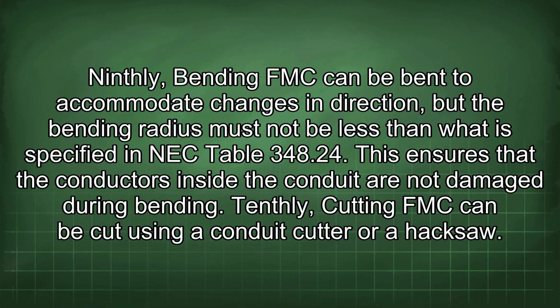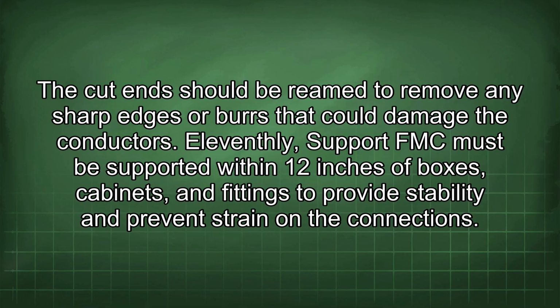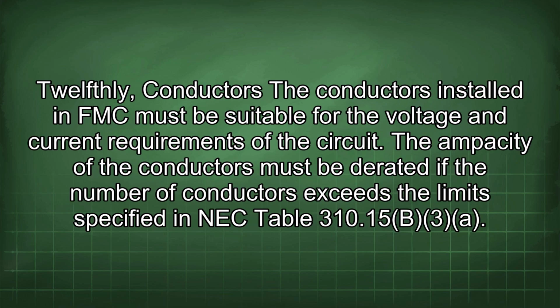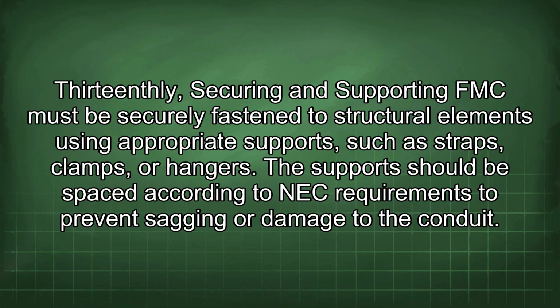Tenthly, cutting. FMC can be cut using a conduit cutter or a hacksaw. The cut end should be reamed to remove any sharp edges or burrs that could damage the conductors. 11thly, support. FMC must be supported within 12 inches of boxes, cabinets, and fittings to provide stability and prevent strain on the connections. 12thly, conductors. The conductors installed in FMC must be suitable for the voltage and current requirements of the circuit. The ampacity of the conductors must be derated if the number of conductors exceeds the limit specified in NEC Table 310.15(B)(3)(a).